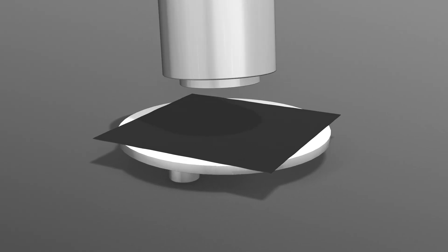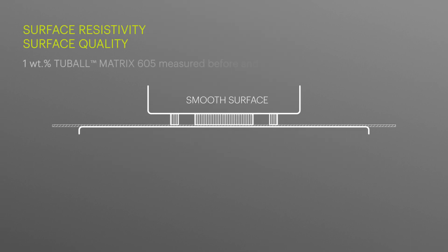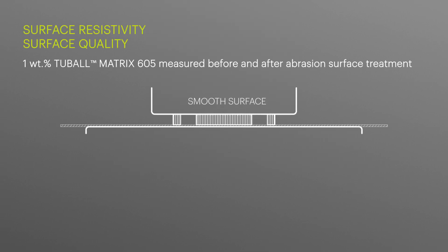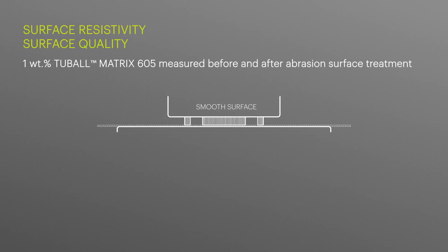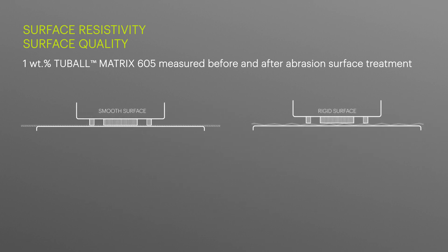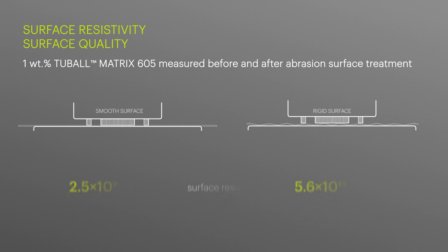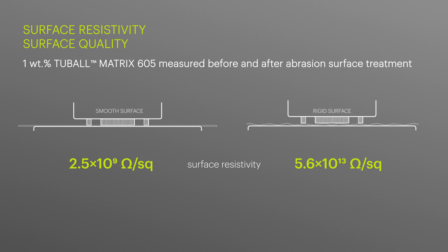As we've learned, with the two-probe measurement technique, the contact area between the electrode and the sample plays an important role and directly affects the obtained resistance values. Because tight contact between the electrode and the sample cannot be achieved when there is an uneven surface, the surface resistivity values measured by the device are greater by several orders of magnitude.